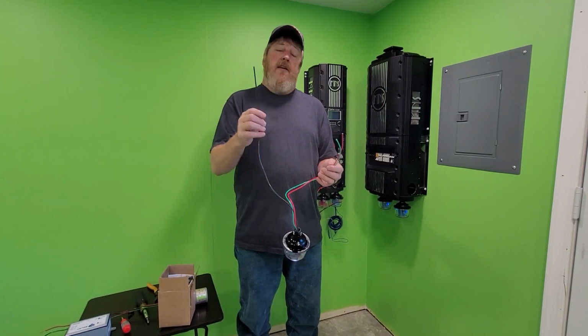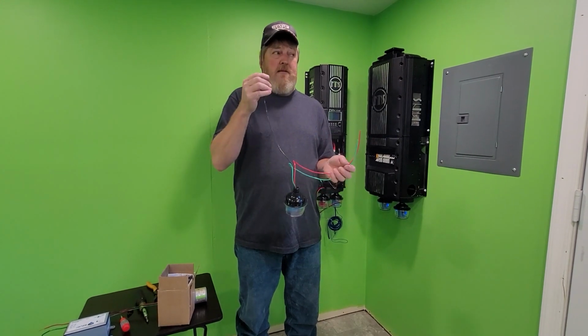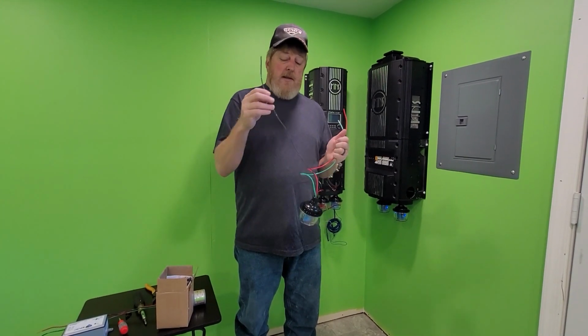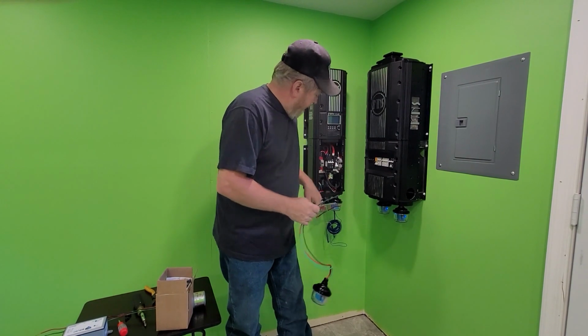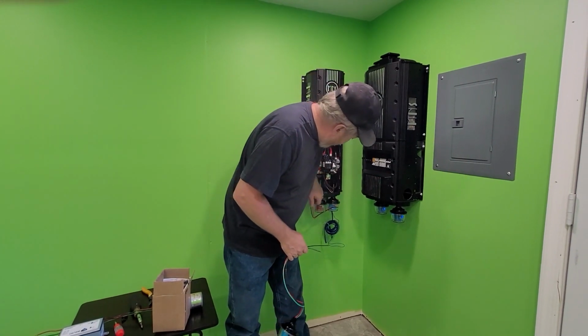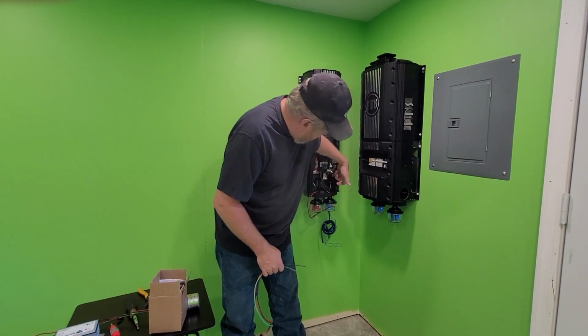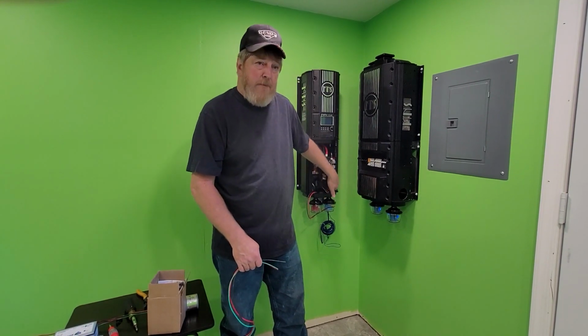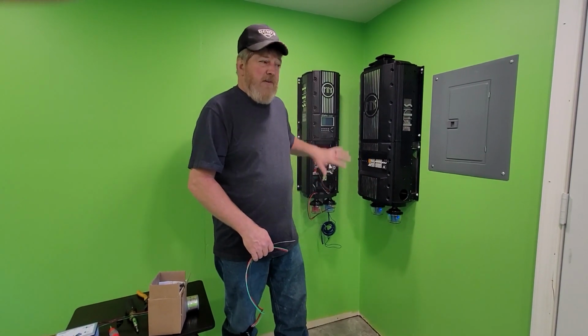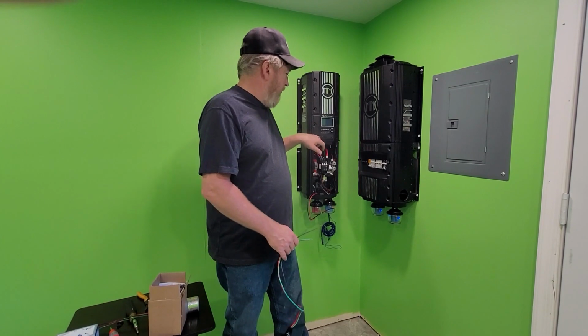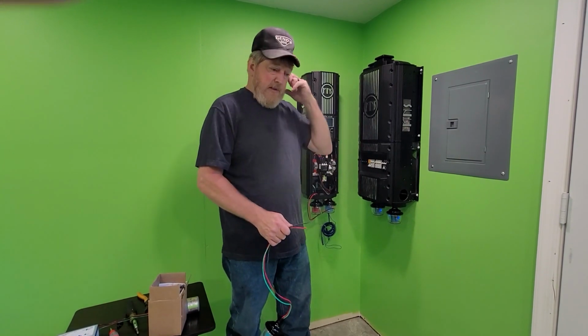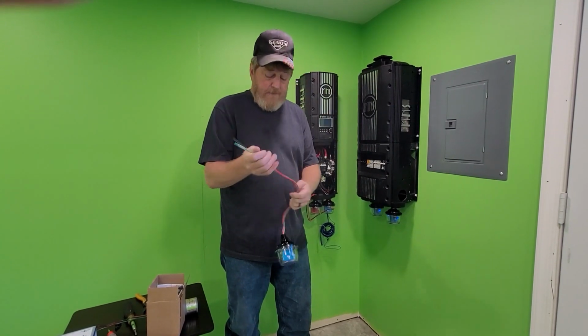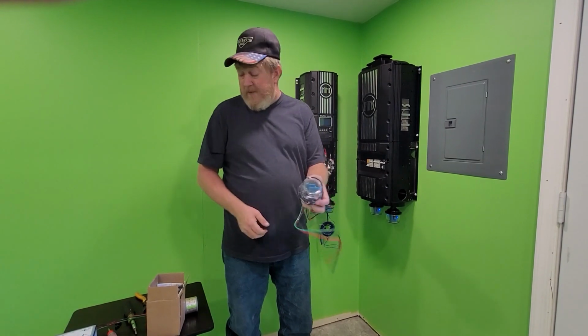If the negative is solidly bonded, it's supposed to be white. If it's reference grounded, then it's supposed to be black. So this black wire that I put in on this SPD right here needs the white heat shrink put on it. This system will be solidly bonded because we're using the new ground fault in the charge controller, allowing us to bond the negative. But that's what you're looking for on an SPD.